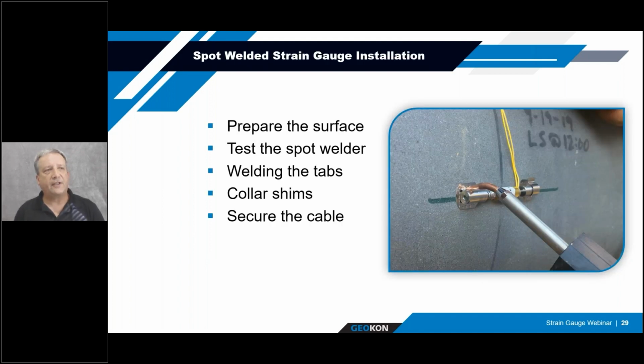To install these spot weldable strain gauges, it's very important that the underlying surface is prepared effectively beforehand. The surface should be clean, dry, flat, and free of any rust, grease, or pitting. It takes a fair amount of time to prep the surfaces and make sure it's all ready to go.